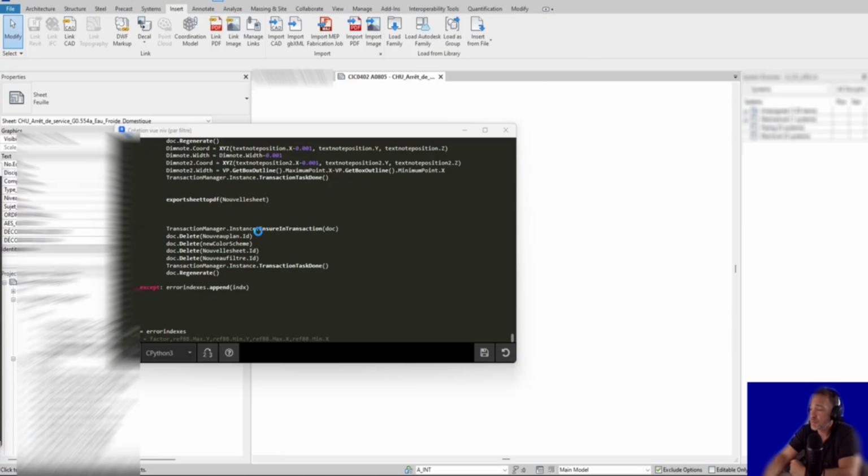So what I did basically is a script that detects every device, I would say every element that is mechanical equipment, plumbing fixture, and so on, every device that gives a service to a room. And for every device, I follow the piping, ducts, or cable network to find the nearest service interruption device.